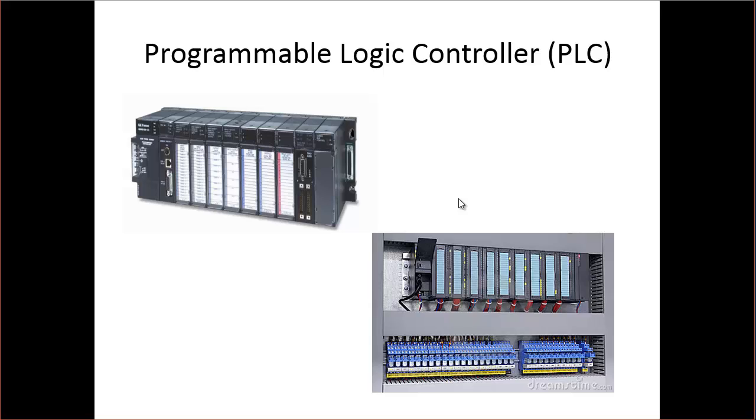In the heart of all this is the programmable logic controller. And a PLC is a small industrialized computer that is made specifically to measure and control real world processes. So let me mark this up a little bit. So a PLC right here as you would see, right here is a CPU, this little card right there. These cards plug in, if you look right here, there's a back plane. So typically you put this back plane on the wall or in your cabinet. And actually I made a mistake here, this isn't the CPU, this is the power supply. So usually these things run off of 24 volts DC and so you have a power supply in here. Then you have the CPU.